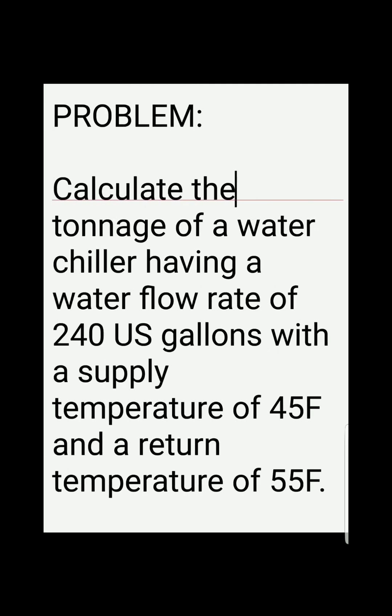So it's a calculation problem here. Calculate the tonnage of a water chiller having a water flow rate of 240 US gallons per minute, with a supply temperature of 45°F and a return temperature of 55°F.